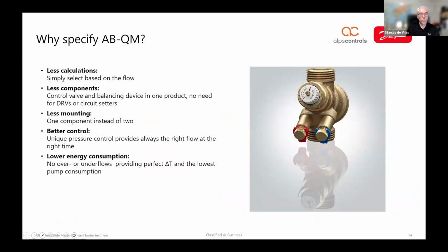Normally, depending on what your solution is, but conventionally you would have a control valve with either a double regulating valve, so something you actually have to measure and set, or an auto flow or circuit setter, and that has two components. Two components also need to be installed in the installation, so that is also time consumption. Time is money. So essentially, we're putting two functions in one: the automatic balance in the valve, together with the control, and you always have the perfect control.